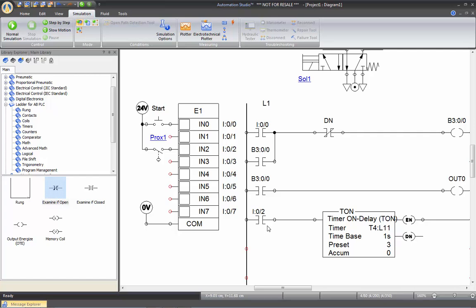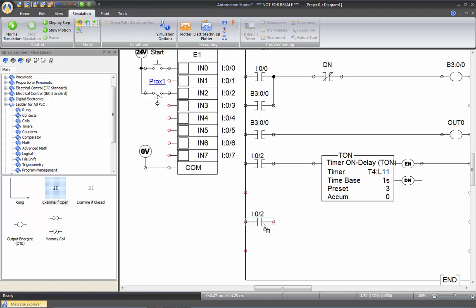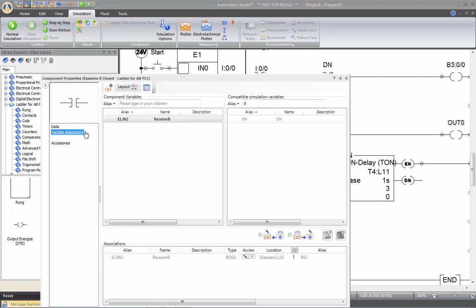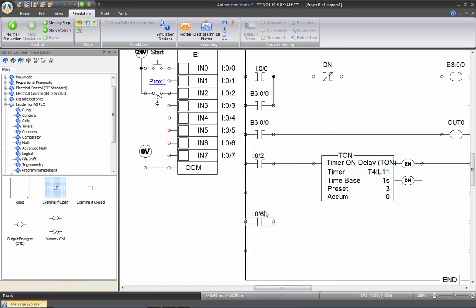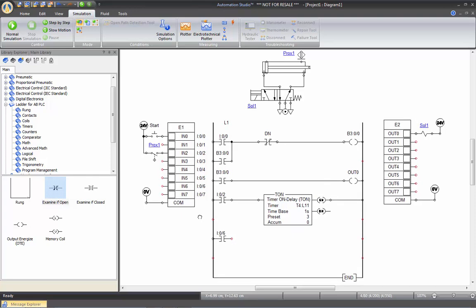So for example, if you copy this contact and you want to link it to input six, you click twice, you go variable assignment, you go input, and if you click twice on input six, you'll see that now the link is made to input six. You do not have to change the addresses to be displayed. Once you set the component to display the address, if you copy that component, it's going to remain the same. Therefore, if you want, you can create your custom library like we showed you in a previous video. And you can have a section called PLC, where you can actually drag your card preset with all the addresses, as well as the contact to display the address instead of the internal ID.